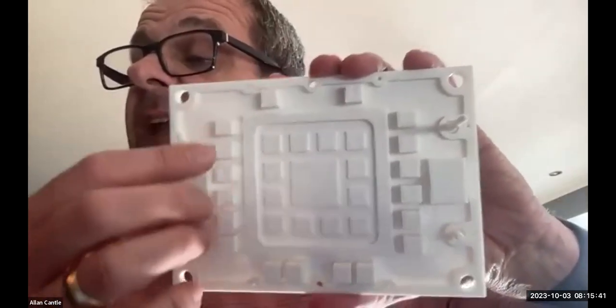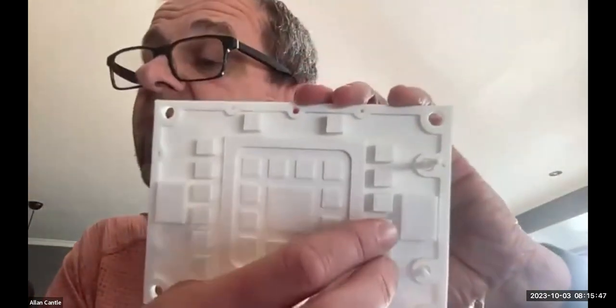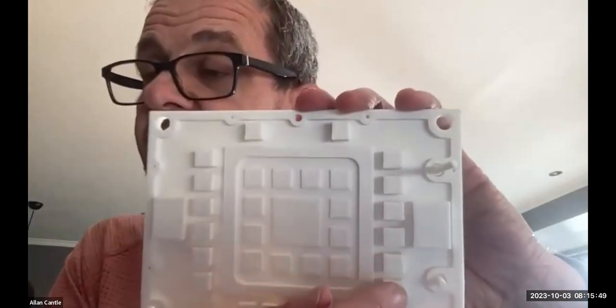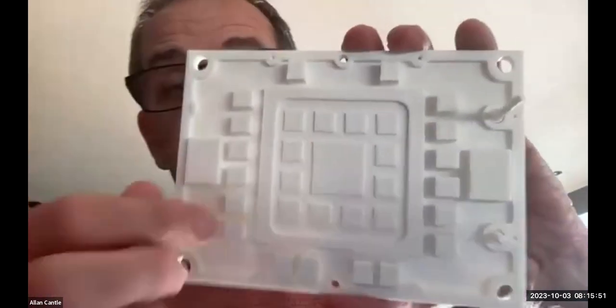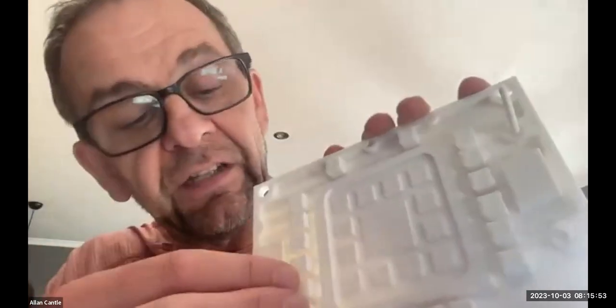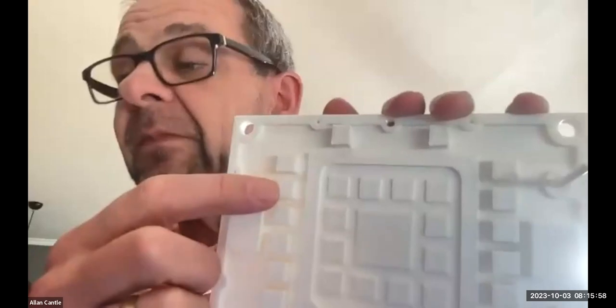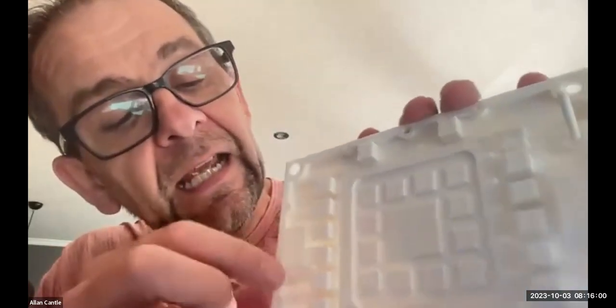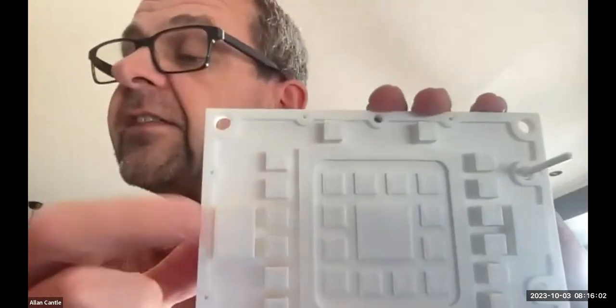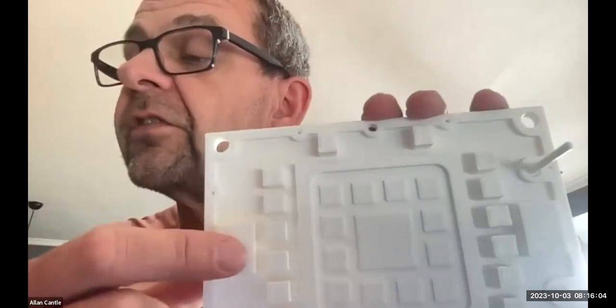It's just a mock-up, and the power bricks that we're choosing to use look like the industry standard now. I don't know if OCP was involved in this or just the hyperscalers themselves, but there seems to be a nice power supply format. Each one of these little bricks is 130 amps capability. And then they've also got these 48 volt to 12 volt converters as well. Seems to be an industry standard footprint.